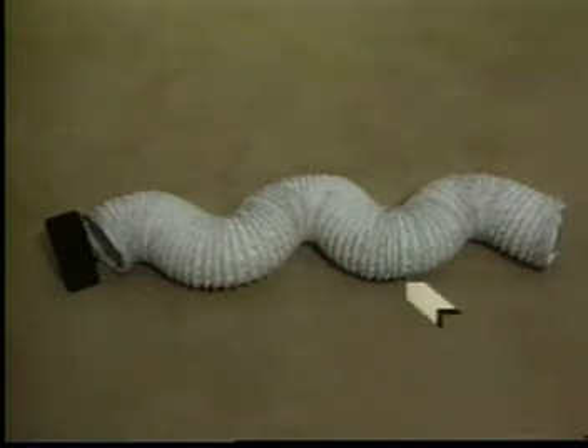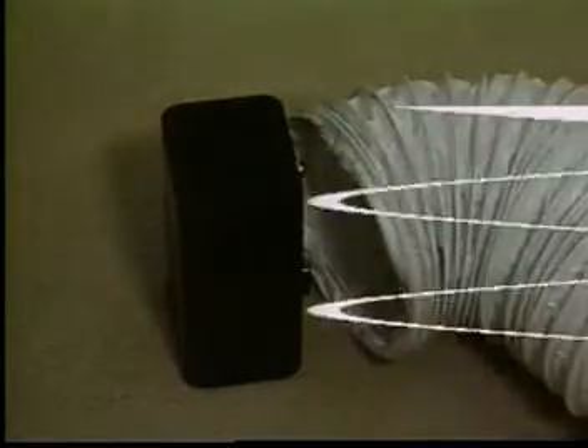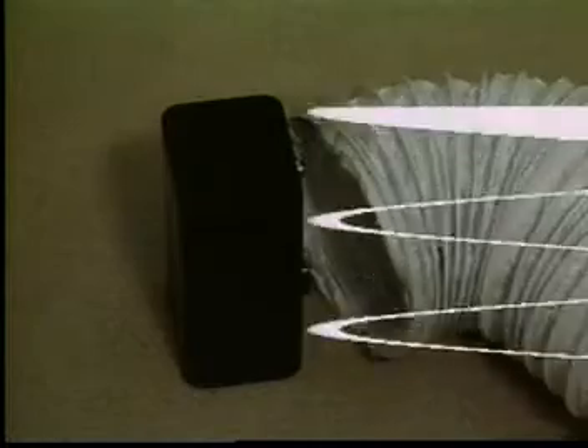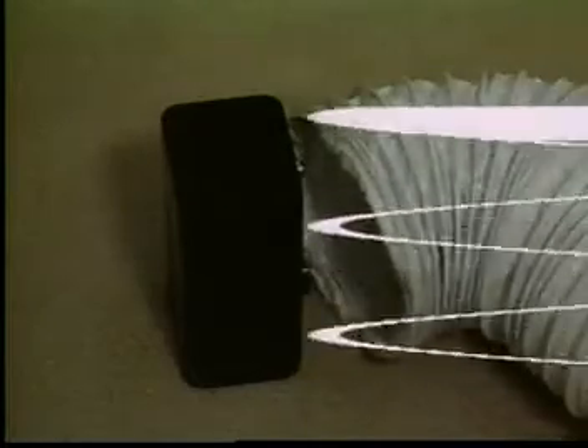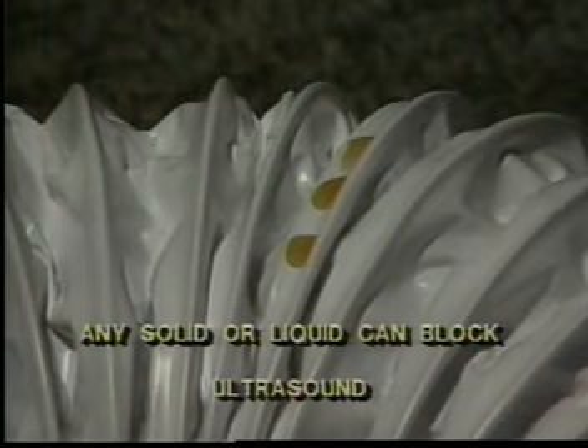Second, if there are a number of bends in the test surfaces, the ultrasonic signal will dissipate, dying out completely after 3 or 4 bends. If this occurs, use more sound to compensate. If using more sound doesn't work, you may need to revert to the pressurization method. Next, remember that any solid or liquid can block ultrasound. If there is any liquid that could inhibit the detectability of ultrasound in the test area, it should be cleared. You can clear it by simply blowing it out with air.